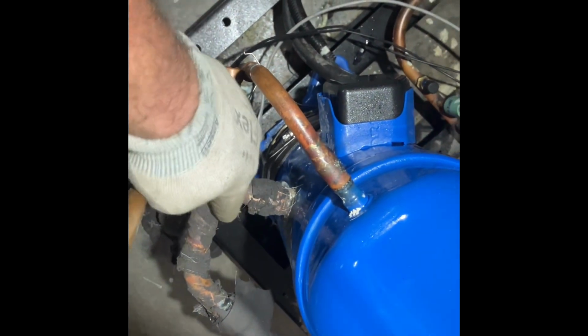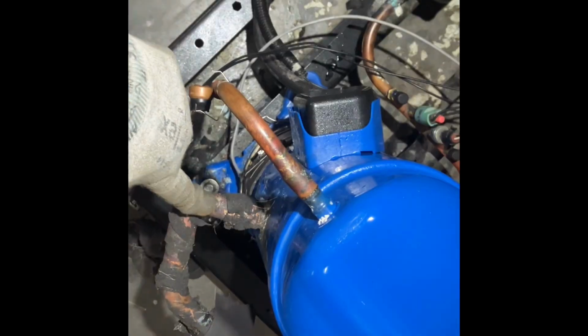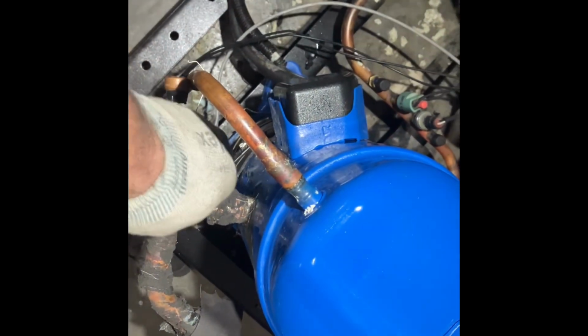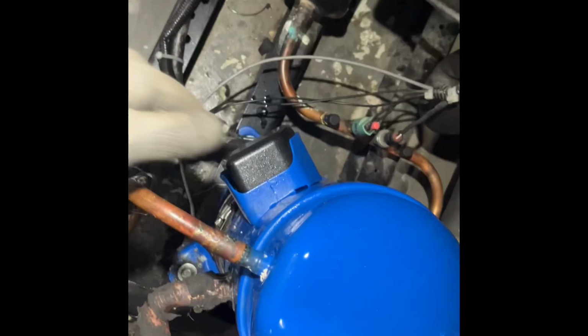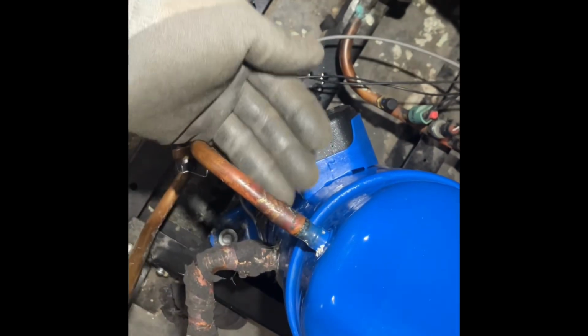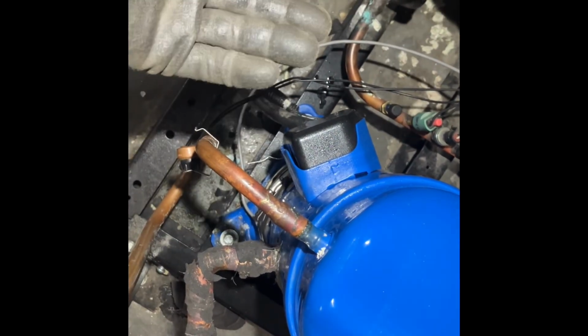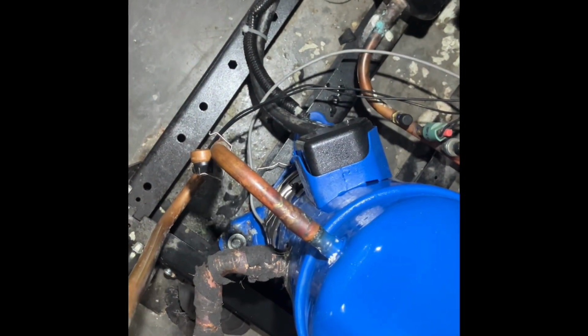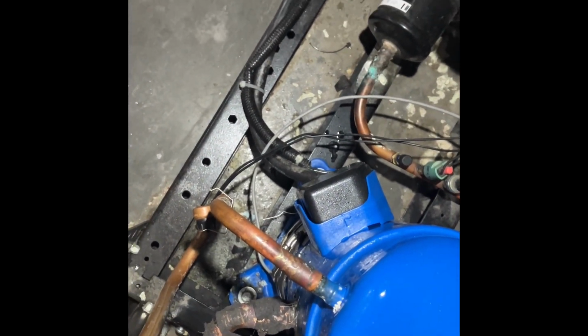I already pulled the insulation back because we had some problems with this guy leaking before. This is all pretty clean. The only thing that gives me a little concern is this discharge connection right here has a little bit of oil on it. But again, who knows? You never know until you get the nitrogen on it.